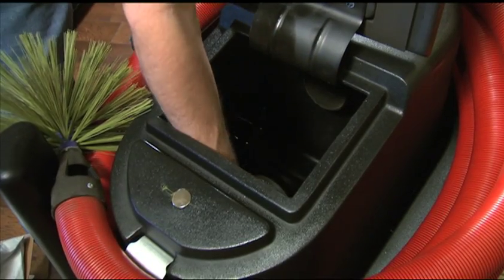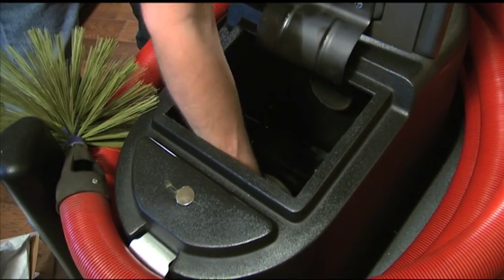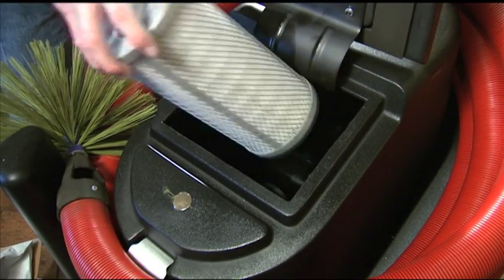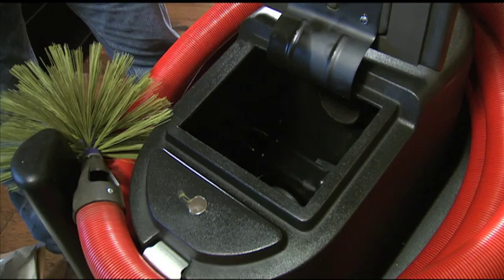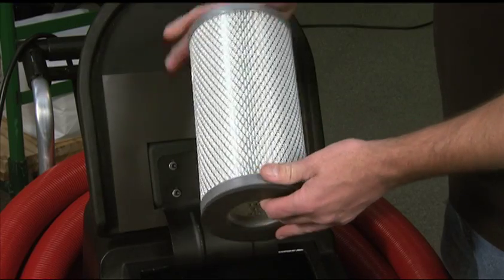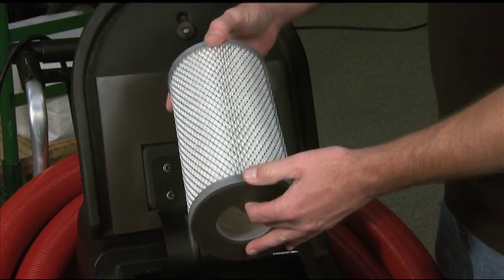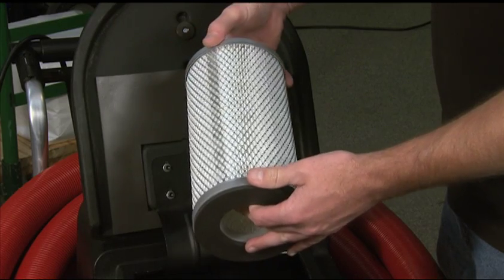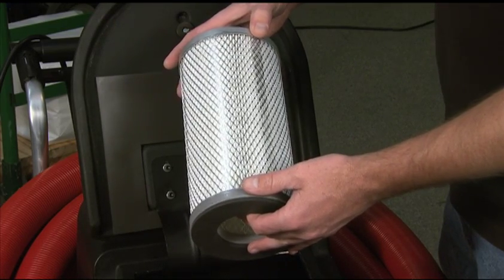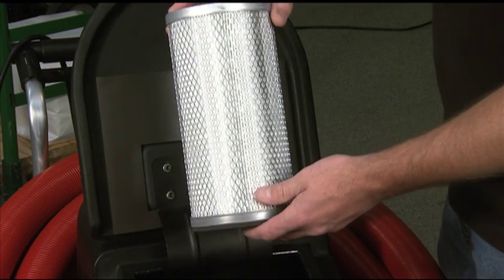The next thing is your HEPA filtration. Okay, the only way to clean these is with compressed air from the inside out or contact vacuum from the outside. Never get these wet and don't beat them on a wall. The end cap or glue could break and the end cap could come off, so don't abuse them. Make sure your technicians know not to get them wet.